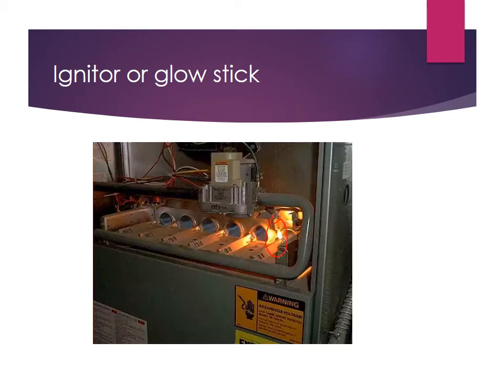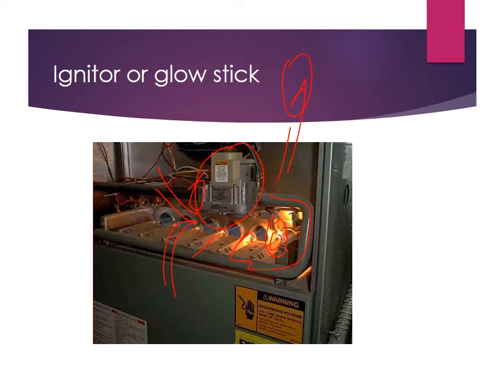Here is the glow stick heater. As with the gas valve — a certified plumber must connect your gas valve to the gas line; we are not allowed to do that ourselves. Gas flows through the jets, and you can see the jets pumping gas inside. There is also primary combustion air coming in from the room. Air is being pulled in by the inducer fan, which draws air along with the gas. The glow stick turns on, lights the first jet, and all of them follow right away because gas is very sensitive to heat and burns quickly.